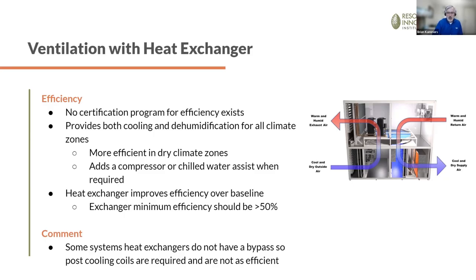The heat exchanger provides an efficiency baseline. It provides, I hate to say it like this, but free cooling, if you will, free energy from that exchange. And because these are enthalpy wheels, typically they're going to have an efficiency over 50%. If it's just a sensible wheel, not doing any moisture exchange, that's when you get into the lower efficiencies. Now, you see in that picture here, it's going through the wheel, and you see some compressors. When it's going back into the space, that air going through the evaporator is cooler and drier. So the compressors are not quite as effective. As I said before, as the temperature and humidity go down, the capacity of refrigeration systems is not as good. They decline.